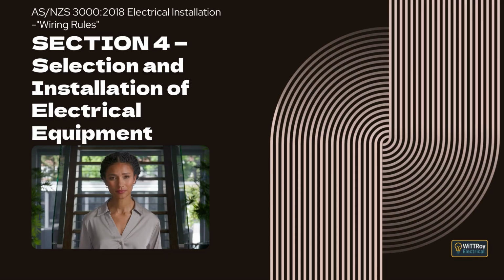It explains that wiring forming part of the equipment itself is considered equipment wiring and must comply with the relevant product standard, or ASNZS 3100 where no product standard exists, and that certain accessories must not be used where the connection point is not readily accessible. Clause 4.3.2, Direct connection. This clause introduces direct connection methods.